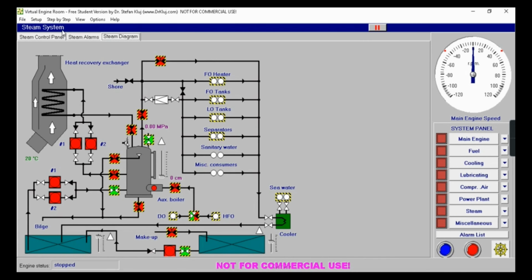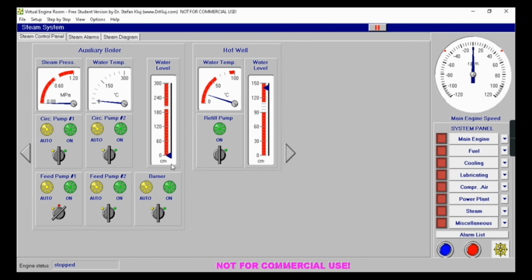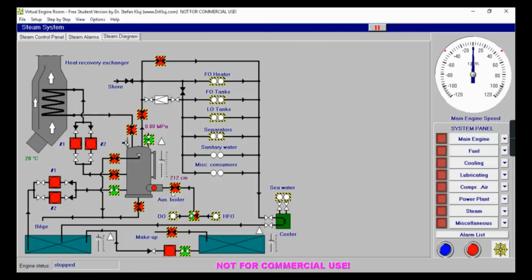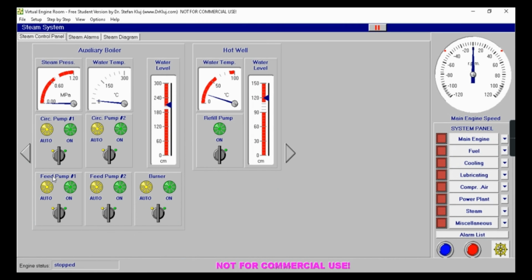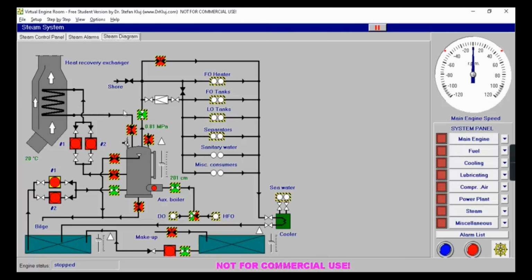We will now fill our auxiliary boiler by opening these valves and starting this pump. Once the level reaches normal range, we will close the pump. We will now open the auxiliary burner fuel inlet valve and switch the following to auto. And then open the auxiliary boiler main valve.